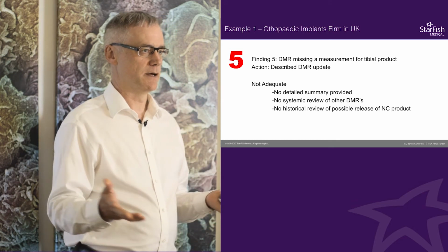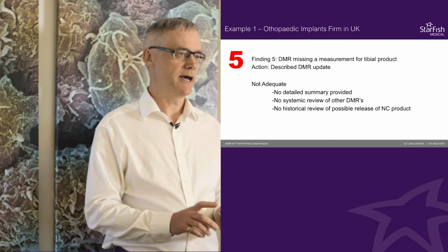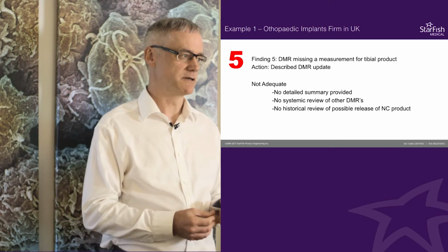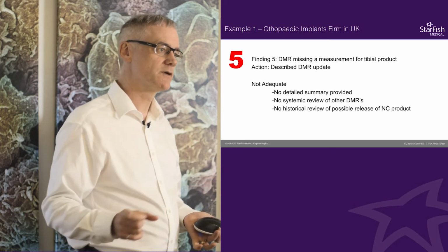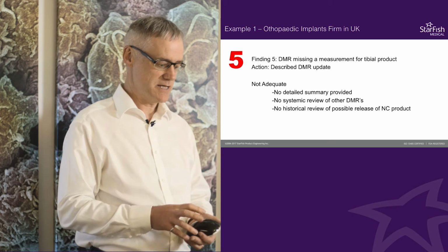The company made their device master record update and sent a description of that, and the finding was not adequate because it was only a summary result. It didn't give very specific detail. There was not enough detail to satisfy them. There was no systemic review of other device master records to see if this problem affected other products they had, and there was no historical review. So there are those two things again. It's really the second step, right?